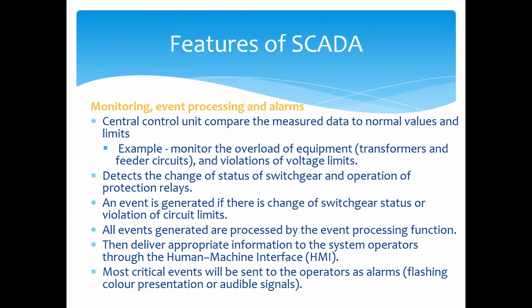The central control unit compares the measured data to normal values and limits. For example, it monitors the overload status of equipment, transformers and feeder circuits, and whether there are any violations in voltage limits. It detects changes of status of switchgear and operation of a protection relay. An event is generated if there is a change in switchgear status or a violation of a circuit limit described above.